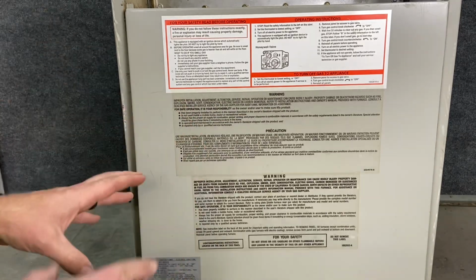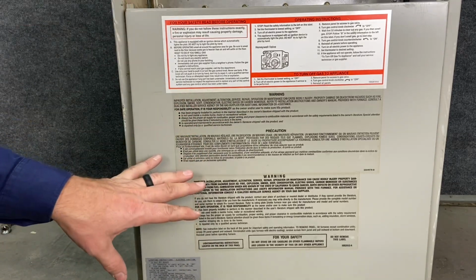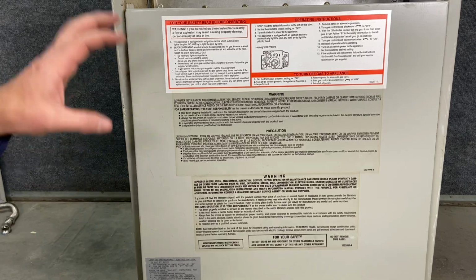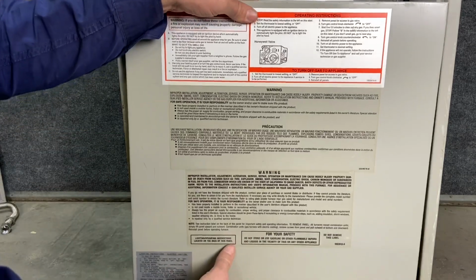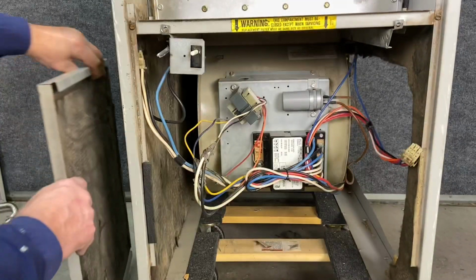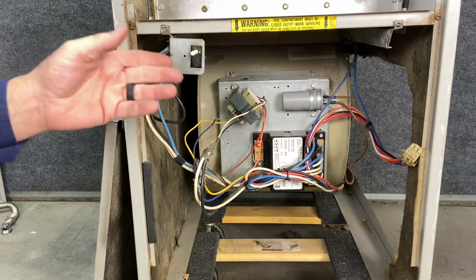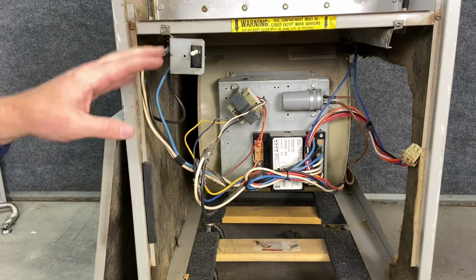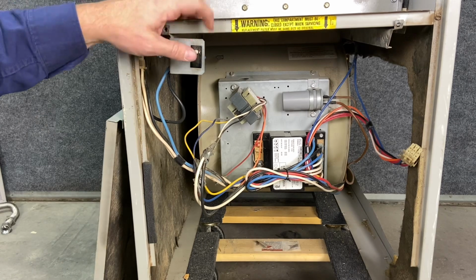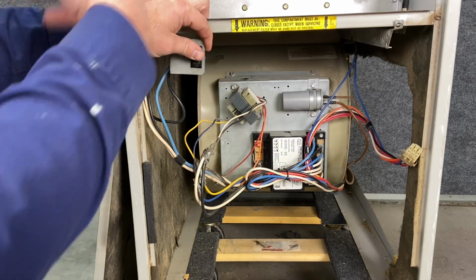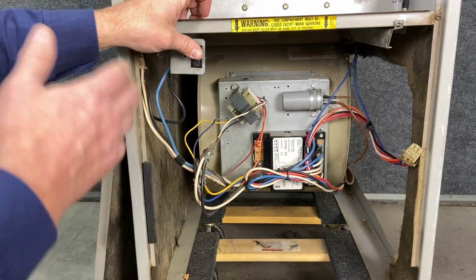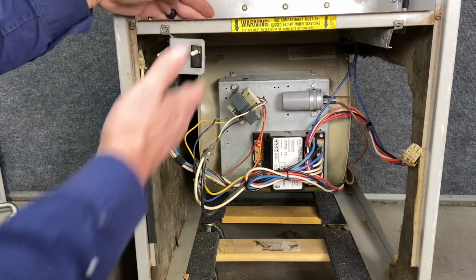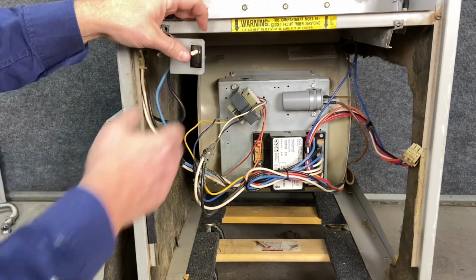There's so much information in here. People overlook this door so much, but it is a key part of making sure that furnace is safe. That's why we have this door safety switch, also called a door interlock. A lot of times when people are working on this furnace, they'll put tape on this to hold it in so they can do their checklist. I have a magnet that's on an angle, but that doesn't work for this one because there's not a great way for it to hold on.